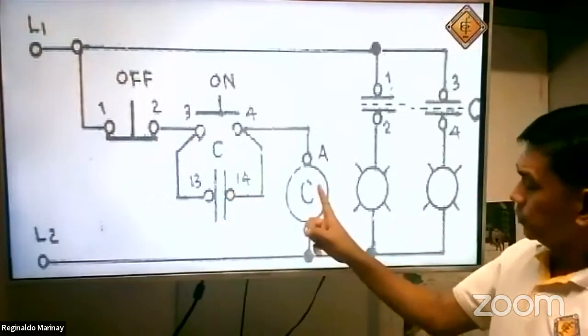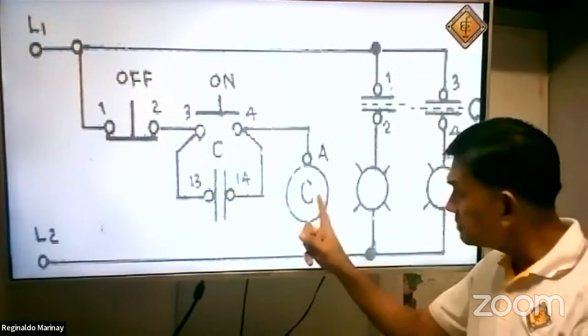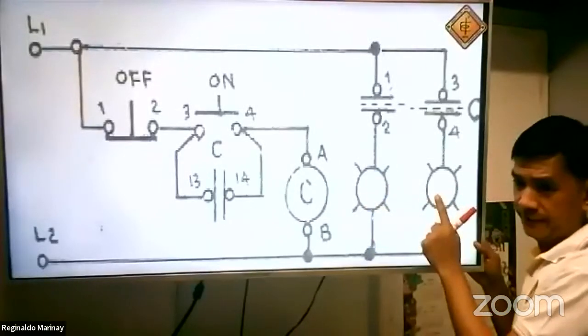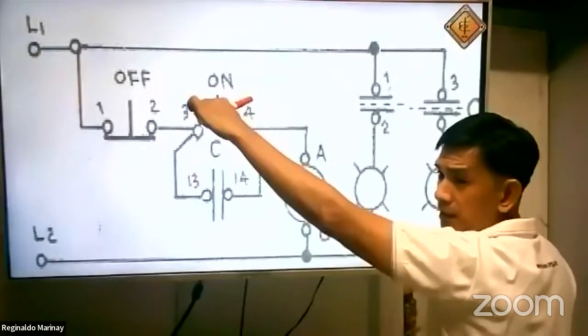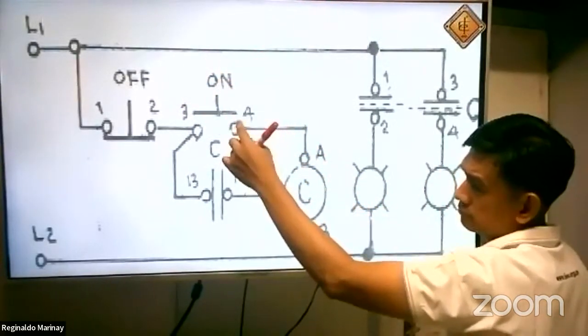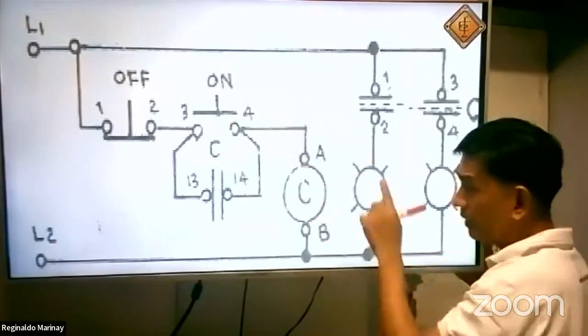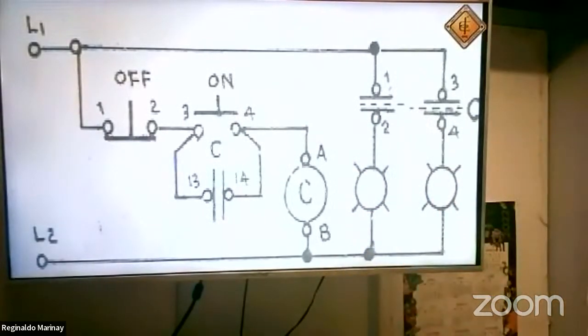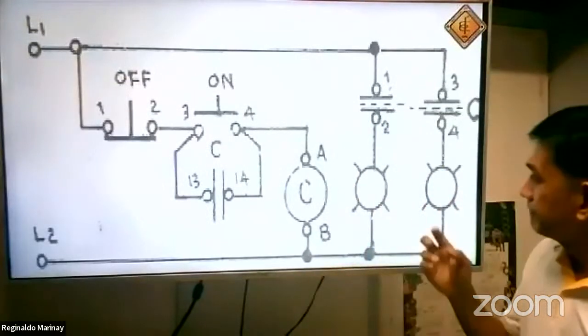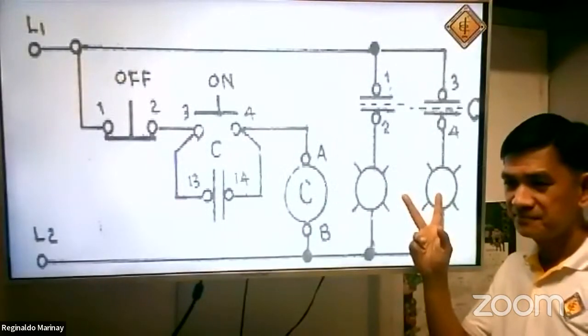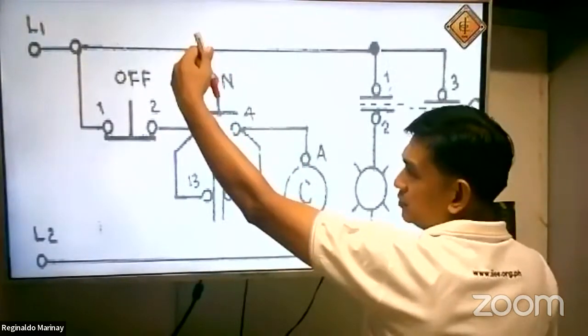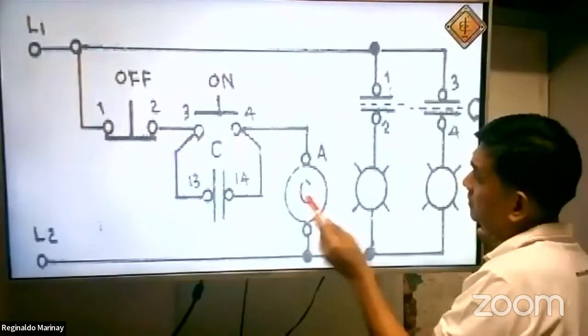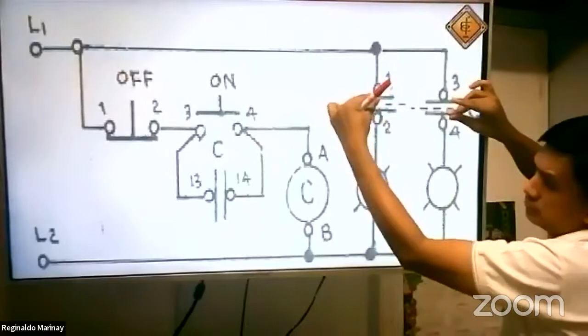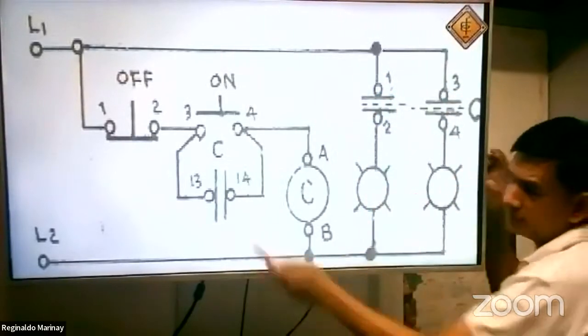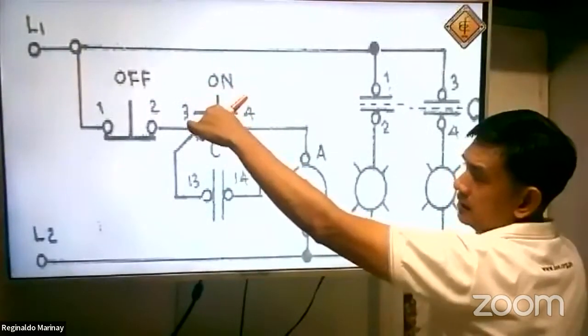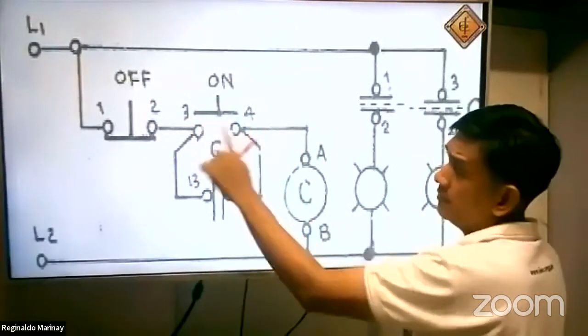So, as long as you energize this holding coil, continuously energizing this holding coil would mean continuously energizing your 2 lamps here. But once you depress this one, okay, once you release your finger, pump, is there still a current flowing to the bulb? That is my question. Is it still energized, the 2 bulbs? Again, I will press this push button down, tap. The current will flow here, energizing your holding coil C. This will become energized simultaneously. Tap. The current will flow here, energizing this now. At the same time, this will become closed. Once you press this one, now, if I'm going to release this one, tap, of course, this will become open.